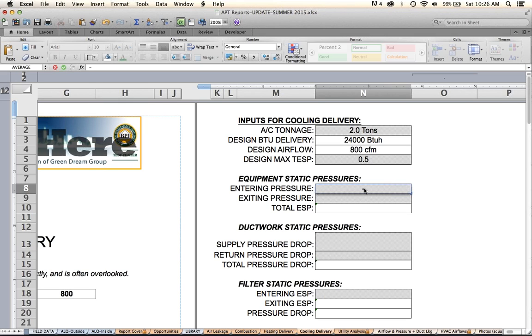The entering pressure at the equipment is going to be after the filter, between the fan, the blower, or the air handler, and the filter, right? That's inside the blower cabinet. And I'm going to make up a number of 0.35. Now, I am not going to do negative 0.35 because that's going to kind of screw up my math here. So I'm going to use all positive numbers for this. Okay, so 0.35 is what I'm putting in here.